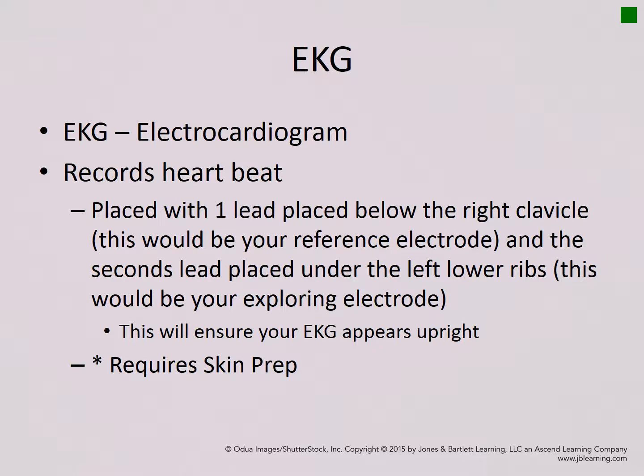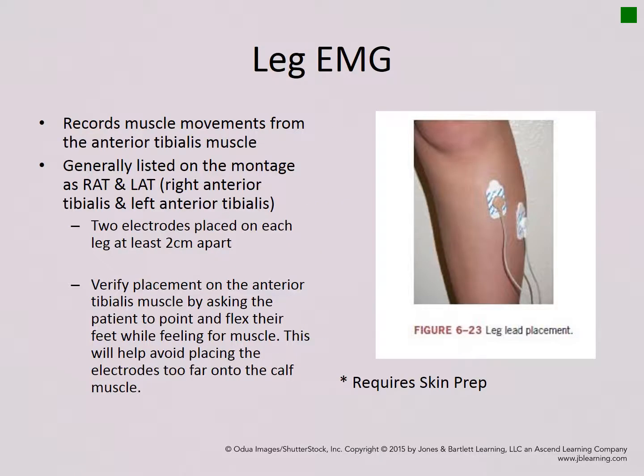Your electrocardiogram or EKG, this is going to record the heartbeat. You place one lead below the right clavicle, and this is going to be your reference electrode, and the second lead is going to be placed under the left lower ribs, and this will be your exploring electrode. This will ensure that your EKG appears upright, and again, this requires skin prep as well. Got to tell you, this finds some ticklish spots pretty easily, so you might want to warn them before you do it that this might tickle. Sometimes I'll even hand it to the patient and let them do it to themselves because you tend to be less ticklish when you do it yourself. So I point out where to do it and have them do it.